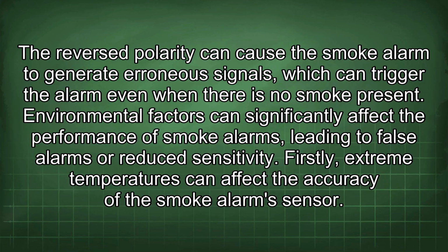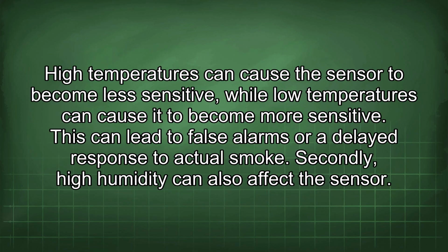Environmental factors can significantly affect the performance of smoke alarms, leading to false alarms or reduced sensitivity. Firstly, extreme temperatures can affect the accuracy of the smoke alarm sensor. High temperatures can cause the sensor to become less sensitive, while low temperatures can cause it to become more sensitive. This can lead to false alarms or a delayed response to actual smoke.